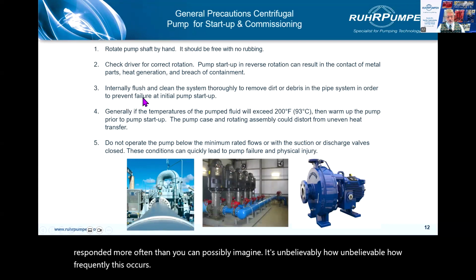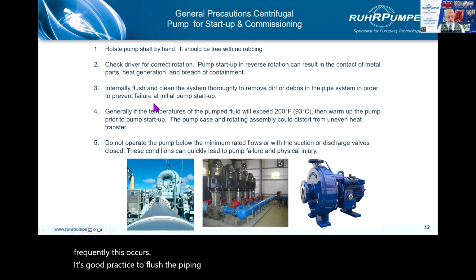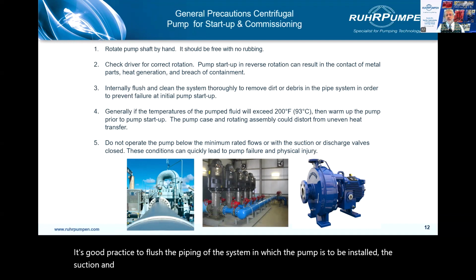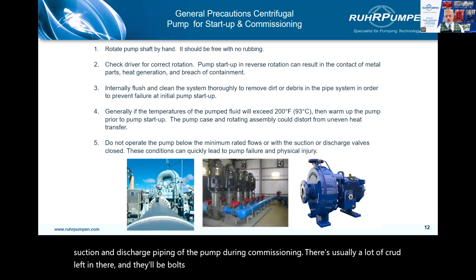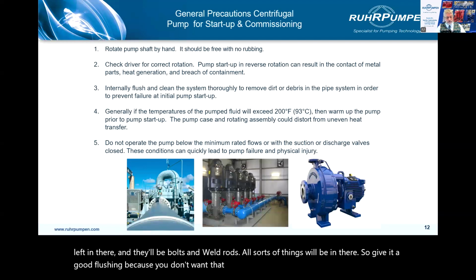It's good practice to flush the piping of the system in which the pump is to be installed, the suction and discharge piping of the pump. During commissioning, there's usually a lot of crud left in there, and there'll be bolts and weld rods, all sorts of things will be in there. So give it a good flushing, because you don't want that going through the pump.